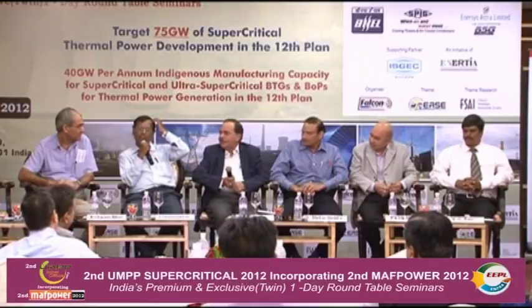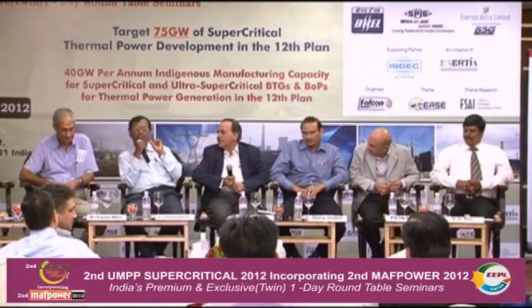Sir, it is like this. If you take very old plants, maybe 30 years back, they were all 110 megawatt sets or 210, operating on a low operating cycle, maybe maximum 130 atmosphere pressure for the turbine. Now we are talking about 250 bar, almost doubling the pressure, obviously giving much improvement in cycle efficiency. Again, those temperatures were not as high; we are now talking about 568, 596. Combined efficiency is much higher. Again, even if you wanted to demolish a 110 megawatt or even a 210 megawatt unit, the net is only 330 - I cannot put even a single 660 megawatt in its place.